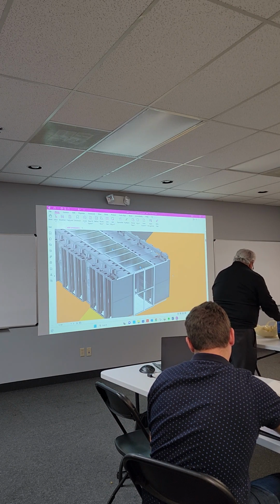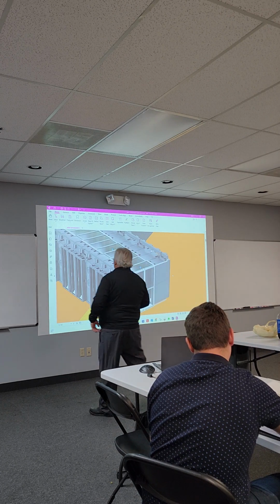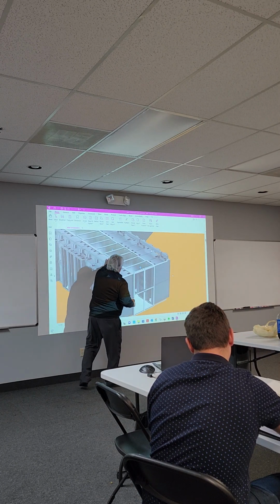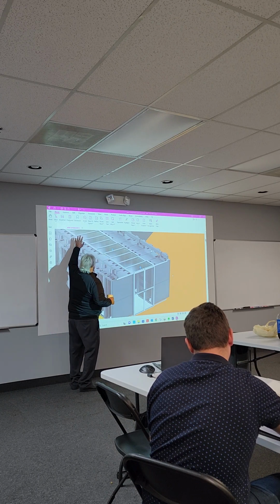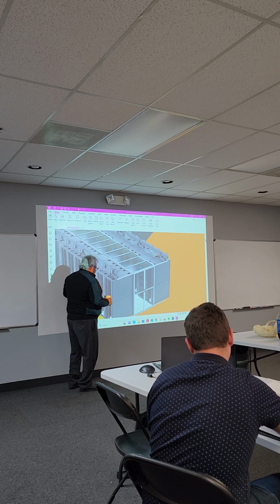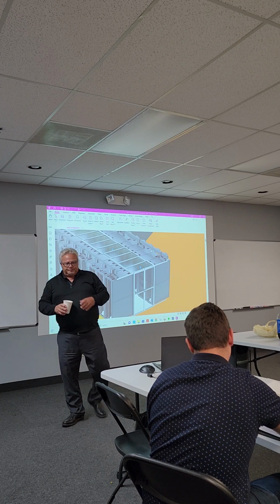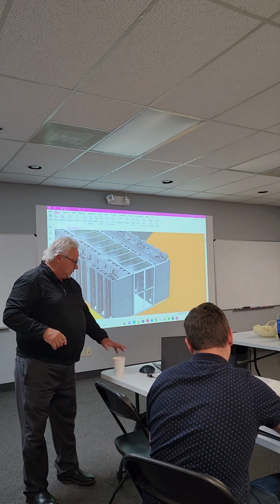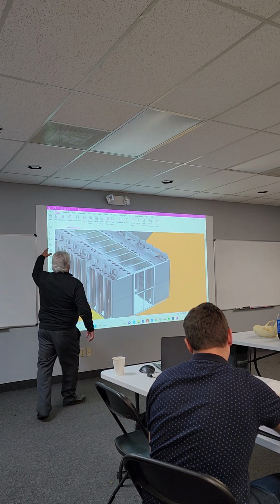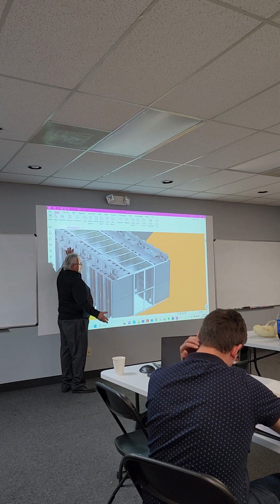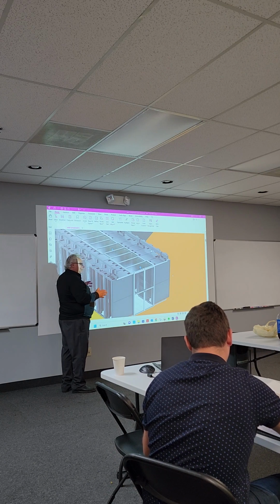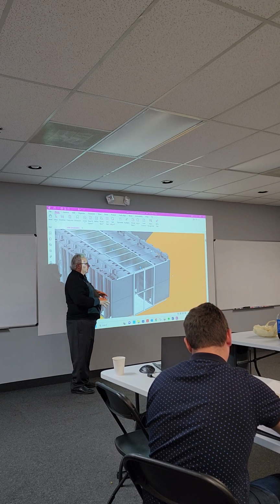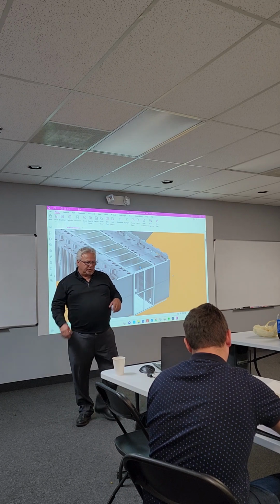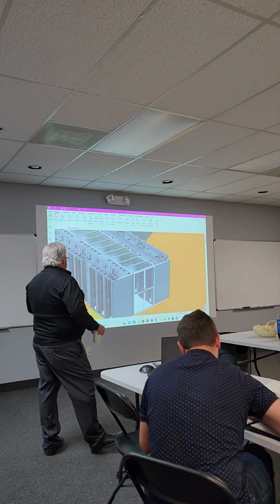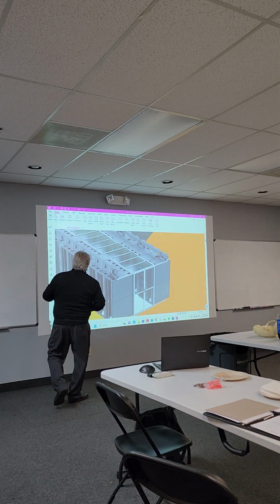So in a case where I had a customer with a setup like this but no containment, they had an air conditioner back here, no other equipment. Their complaint was they didn't have enough cooling in the room, but that unit back there was cycling off all the time. Remember, these are not mechanical people. They have no clue. So it's your job as the technician, the advisor, to tell them what's going on and show them.